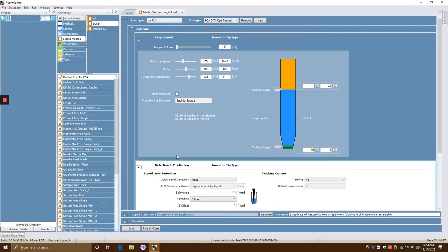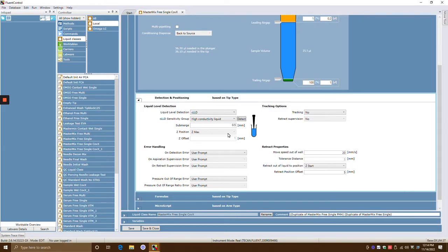Let's go into detection and positioning. If you're using the black pipette tips, those are actually conductive tips. You can use cLLD — that's for using a conductive tip. Conductive tips are used to sense the liquid, kind of like dipping your toe in a pool just to see it's there. You can determine if you have a very conductive, medium, or low conductivity liquid, specify that, and tell it how low to go down and which position you want.